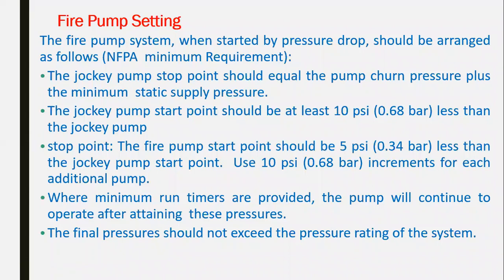Setting for the fire pump, I think we might have talked about this one last time, but it is better to have a refresher for our memory. The Jockey pump starts at least within 10 psi. The set point for the fire pump is 5 psi less than the Jockey pump, so it has a difference of 5 or 10 psi.